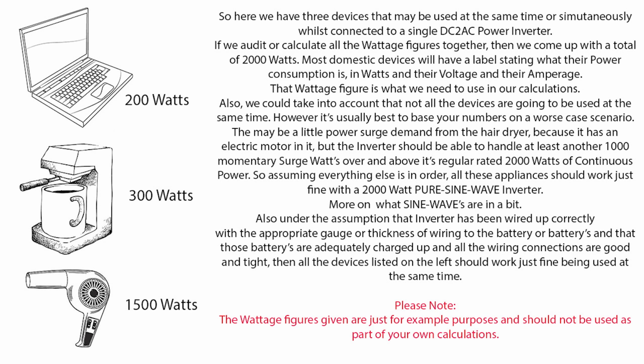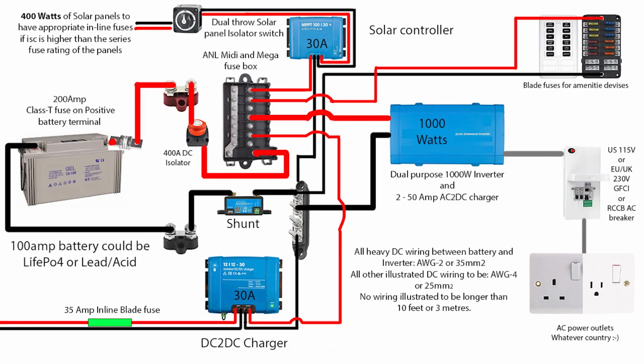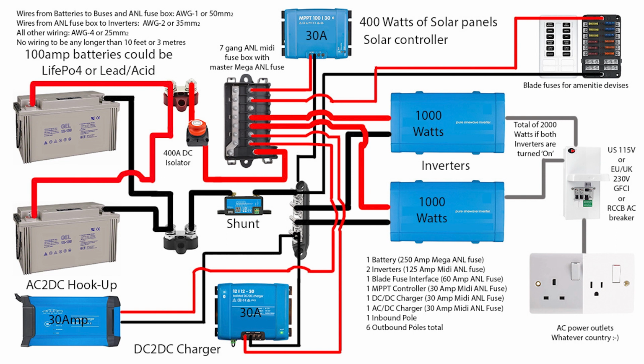In respects to buying an inverter, it's always better to go a little higher in its continuous rate wattage than you think you might need. Keep in mind future growth. It may be possible that in the future you will need more AC power, so you might need to upgrade your inverter or add another inverter wired in parallel, if your inverter model supports multiple inverters being connected together. Please read the inverter manufacturer's documentation or make inquiries to see if your inverter supports multiple inverters being connected in parallel. Some inverters can be wired together to upgrade their wattage.